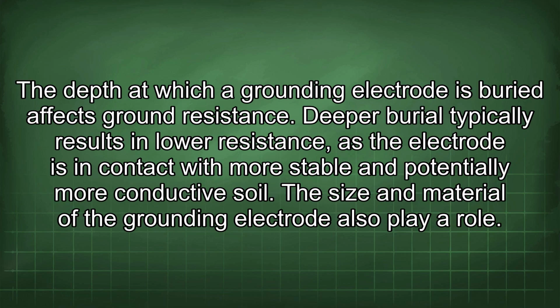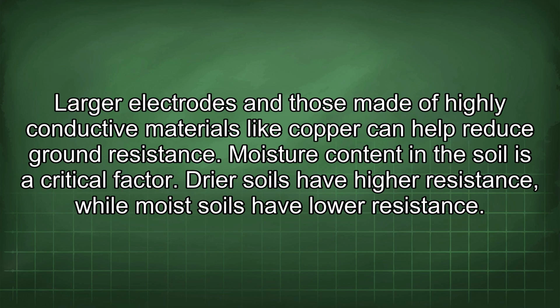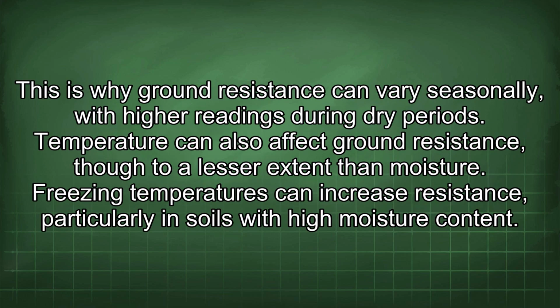The depth at which a grounding electrode is buried affects ground resistance. Deeper burial typically results in lower resistance, as the electrode is in contact with more stable and potentially more conductive soil. The size and material of the grounding electrode also play a role. Larger electrodes and those made of highly conductive materials like copper can help reduce ground resistance. Moisture content in the soil is a critical factor. Dry soils have higher resistance, while moist soils have lower resistance. This is why ground resistance can vary seasonally, with higher readings during dry periods.